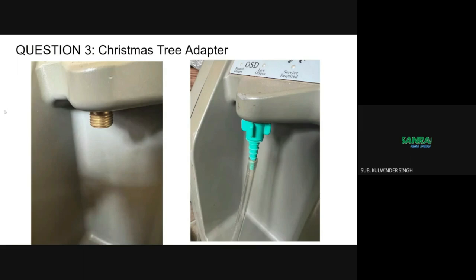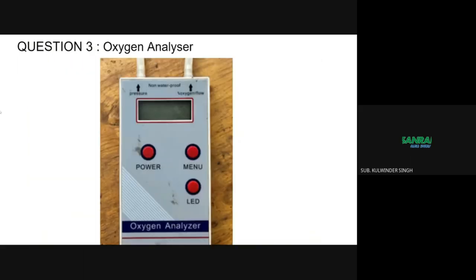An oxygen analyzer is a tool for measuring the oxygen concentration produced by the concentrator. The WHO recommends that an oxygen concentrator must deliver oxygen at a concentration greater than 82%. Staff need an analyzer to check purity and ensure concentrators are delivering oxygen at recommended concentrations; otherwise they might unknowingly use a concentrator giving out low concentrations, which is not helpful to patients.